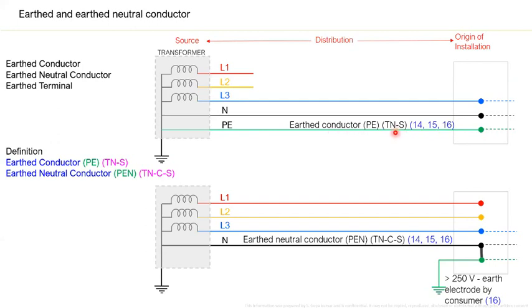There is a fault return path, a metallic fault return path. In case of TN-S, there is a direct path. In case of TN-C-S, there is a link. So as a result of the direct metallic fault return path, the fault current goes back very quickly to the source. Enough fault current flows and your cutout, the fuse, will disconnect the supply.